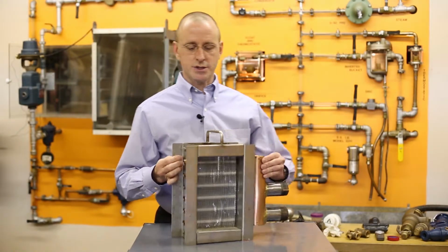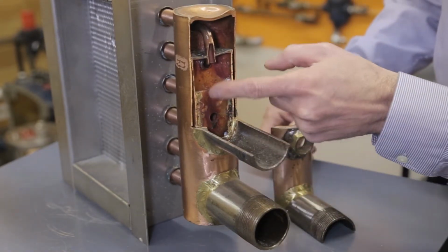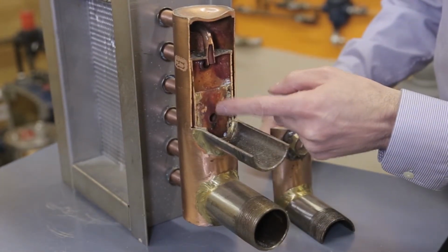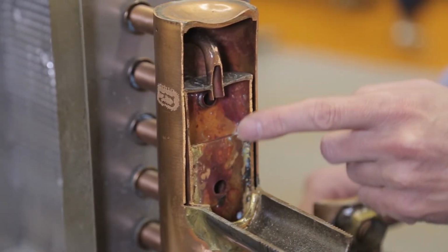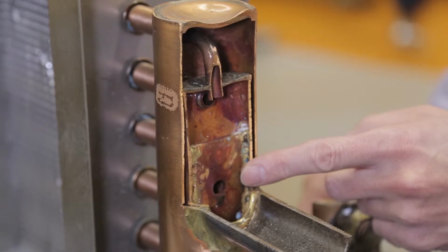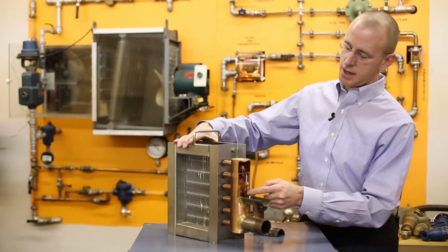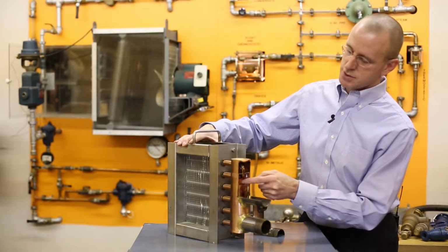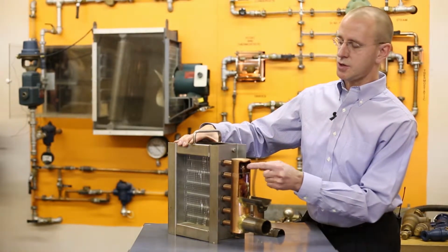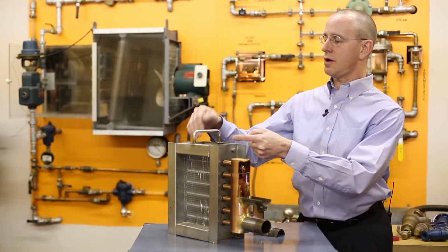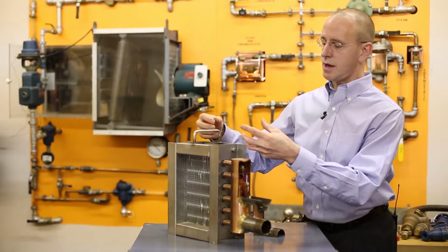So you're wondering how we get steam through the tube area. This cutaway, you can see that the steam goes in here, hits this baffle plate to provide good steam distribution. It's got a header inside of an outer header. This inner header is the steam containing header, which distributes the steam into these smaller diameter tubes. These smaller diameter tubes travel down the length of the coil, and they're perforated along their length to allow the steam to come out to the outer tube.